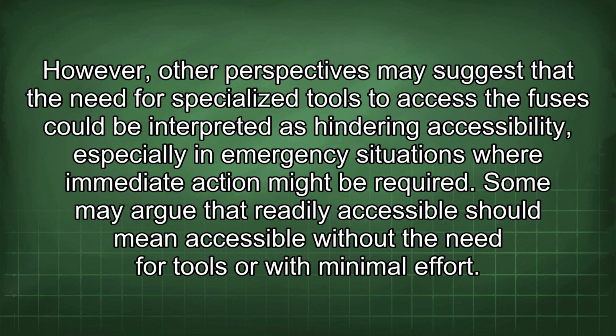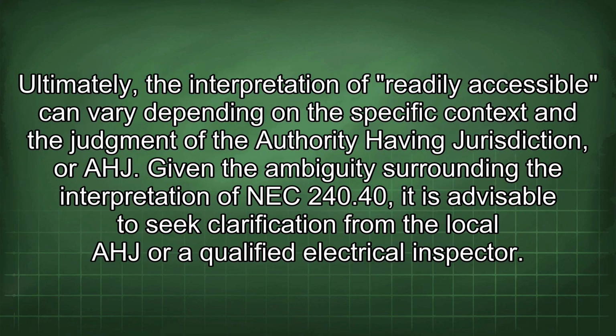work. However, other perspectives may suggest that the need for specialized tools to access the fuses could be interpreted as hindering accessibility, especially in emergency situations where immediate action might be required. Some may argue that readily accessible should mean accessible without the need for tools or with minimal effort. Ultimately, the interpretation of readily accessible can vary depending on the specific context and the judgment of the authority having jurisdiction, or AHJ. Given the ambiguity surrounding the interpretation of NEC 240.40, it is advisable to seek clarification from the local AHJ or a qualified electrical inspector.